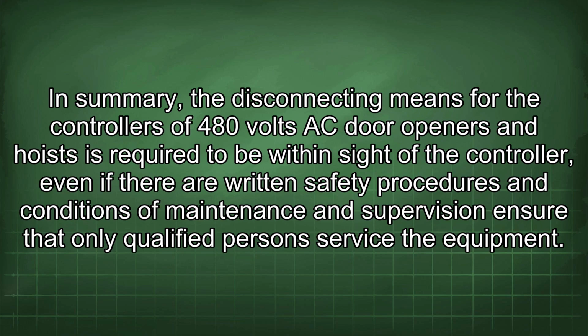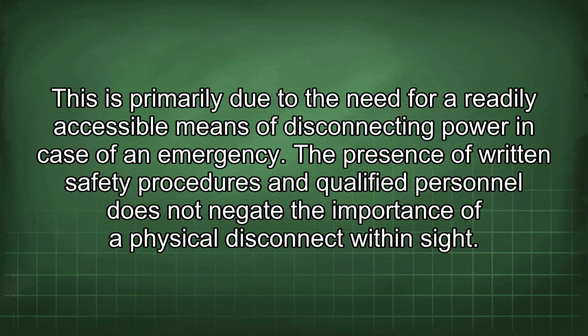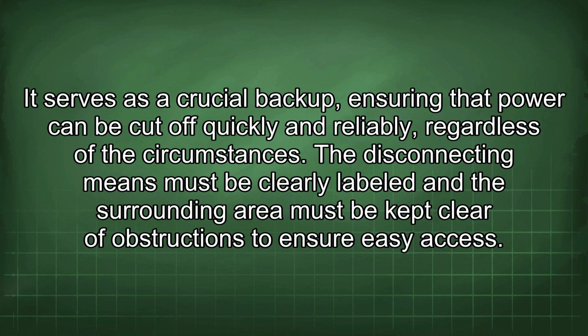In summary, the disconnecting means for the controllers of 480 volts AC door openers and hoists is required to be within sight of the controller, even if there are written safety procedures and conditions of maintenance and supervision ensure that only qualified persons service the equipment. This is primarily due to the need for a readily accessible means of disconnecting power in case of an emergency. The presence of written safety procedures and qualified personnel does not negate the importance of a physical disconnect within sight. It serves as a crucial backup, ensuring that power can be cut off quickly and reliably, regardless of the circumstances.